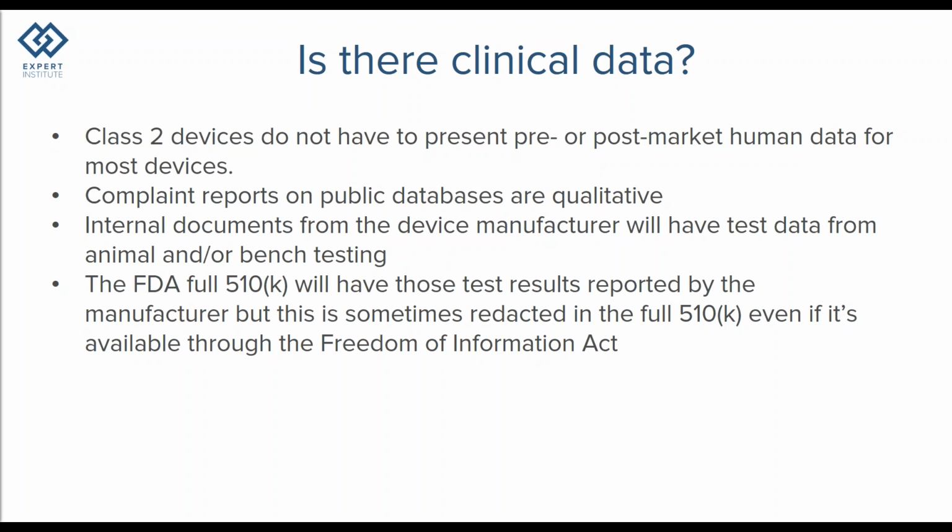The process by which a lot of these medical devices are cleared to market in the US is an application. It has a number, the 510K, and a 510K will typically have bench testing type of data. That's the kind of thing where a manufacturer will have a device, maybe it's made out of some different kinds of plastics or metals, and they'll do corrosion testing and strength testing, and they'll make sure that the manufacturing process doesn't introduce any contamination.